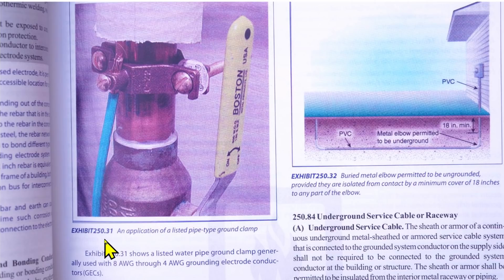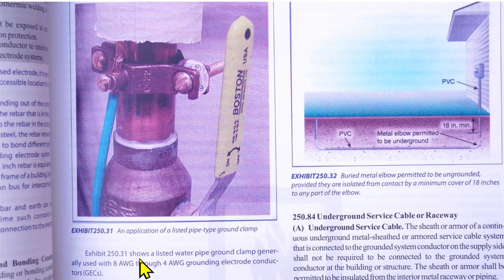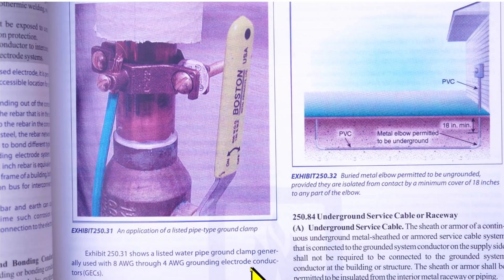This is Exhibit 250.31 from the 2020 NEC handbook. It says Exhibit 250.31 shows a listed water pipe ground clamp — that's right here — generally used with 8 AWG through 4 AWG grounding electrode conductors, or GECs. That's a simple example of a GEC.